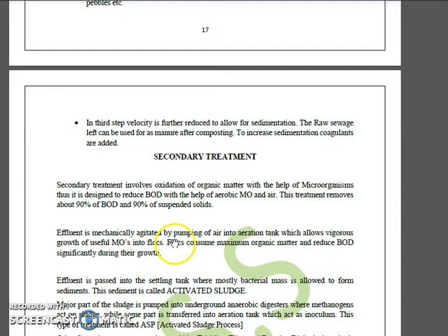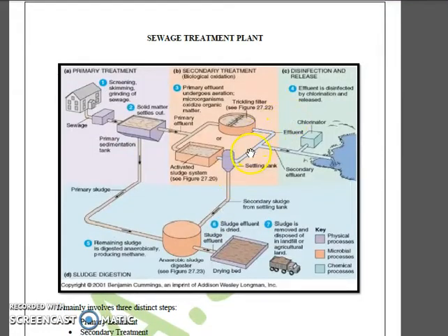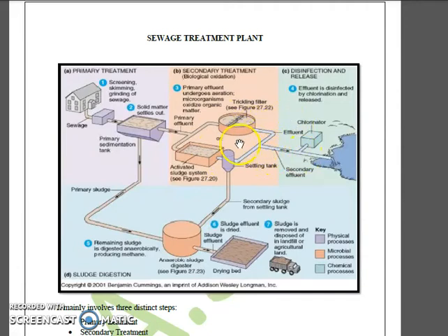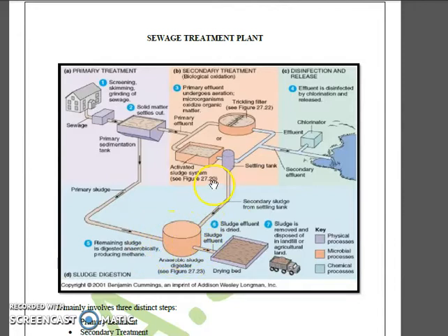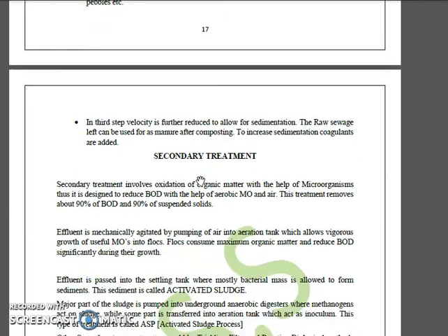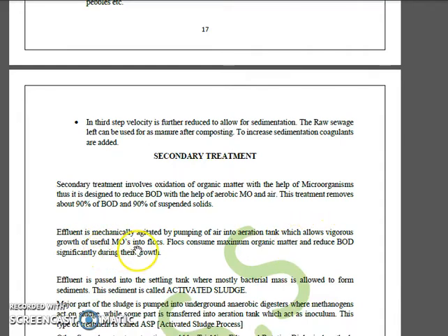After the secondary settling tank, the remaining sludge — called secondary sludge or activated sludge — is pumped into an underground anaerobic digester, producing biogas and organic manure. The effluent is mechanically agitated by pumping air into the aeration tank, which allows vigorous growth of useful microorganisms into flocs that consume maximum organic matter and significantly reduce BOD.